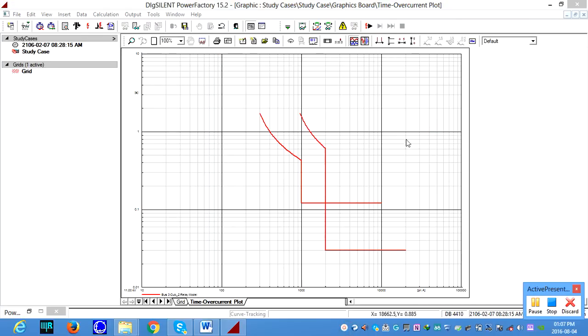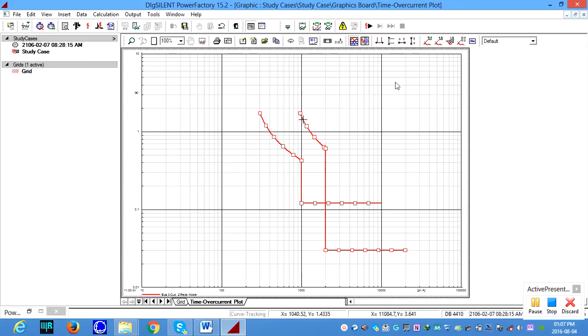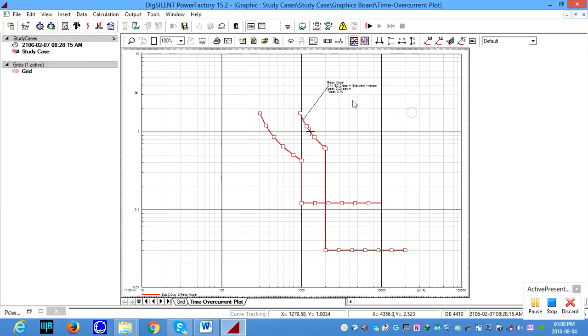Okay, next we need to include the labels in order to understand the IDMT characteristics curve in the time overcurrent plot. First we need to select a specific characteristics curve. And we can go for add label with the defined format to show what characteristics of this relay is. And also if you double click here, it will open the settings of this relay. But we can see from here, this is a phase current 51P1. Okay. So to know about that, we just use a formatted text. And we can say 51P1, relay model, for our understanding, 51P1. Okay, it means it is inverse characteristics.